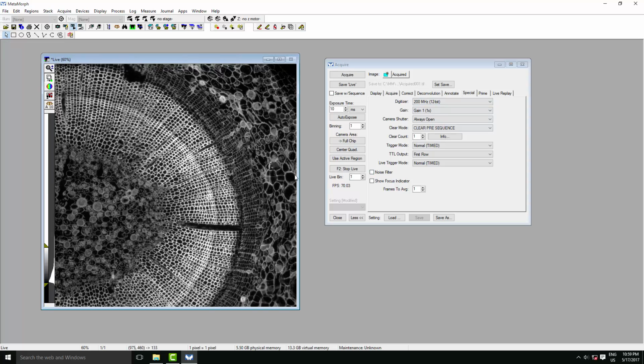So the Prime95B is a back illuminated CMOS sensor with a 1200 by 1200 resolution and 95% quantum efficiency. It's also got really low read noise, meaning that this is a perfect camera for applications that demand sensitivity in addition to good field of view and high speed. So we have an 18.7mm sensor, meaning that we have a really nice field of view, and 11 micron pixels, which are perfectly matched to use a 100 times objective for maximum resolution.